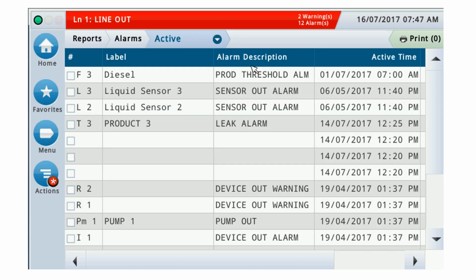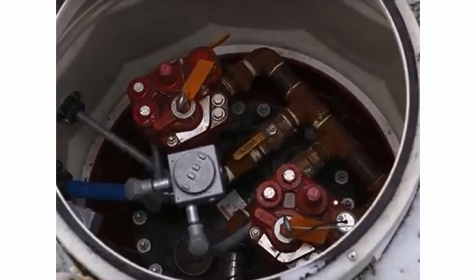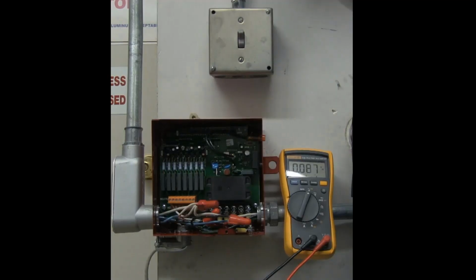Check the alarm report. Are there any line leak alarms or sensor alarms which are programmed to turn off the STP? Verify the proper sensors are programmed to shut off the correct line. Make sure the ball valve from the STP is open. Check the functionality of the STP control box.